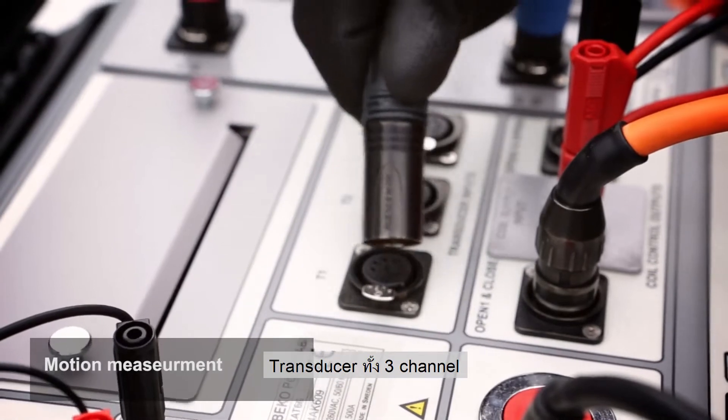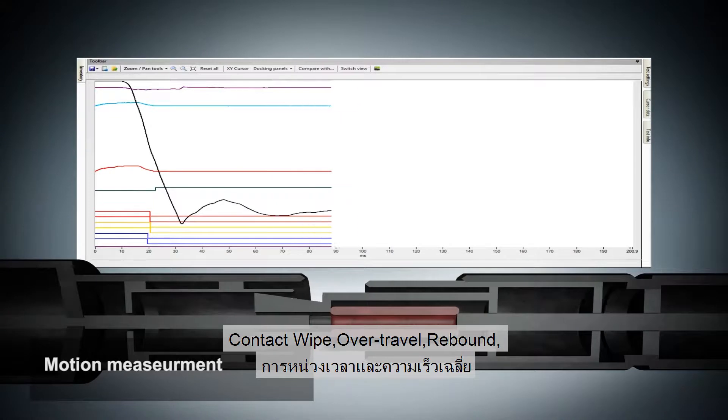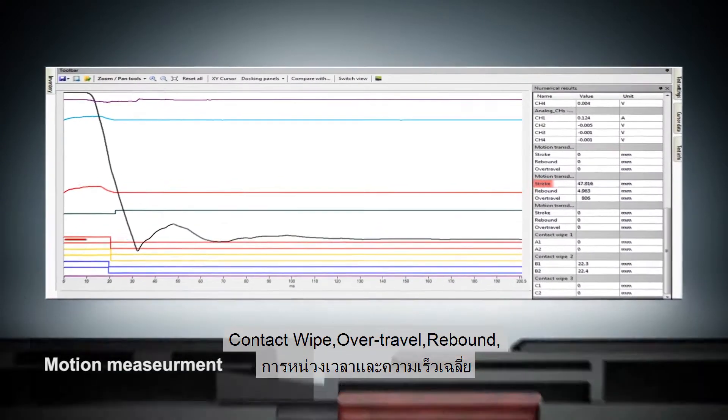The three transducer channels are intended for measuring displacement of the circuit breaker moving parts, contact wipe, over travel, rebound, damping time, and average velocity.